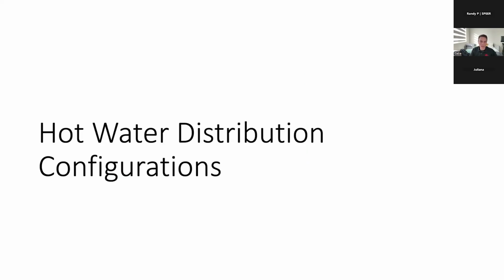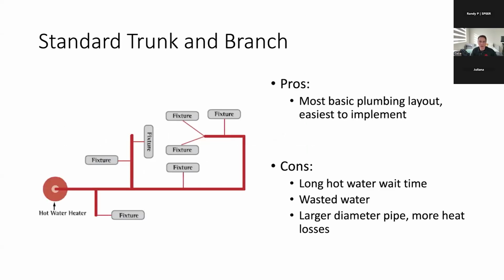So, what types of hot water distribution configurations are there? The most basic kind is what we call standard trunk and branch, or just standard plumbing. This is what we would see in most homes, where you have the water heater on one side, and all of the fixtures are plumbed in series until the main trunk line sort of deadheads at the end of the house. Off of that main trunk line, you have the branches that feed each individual fixture.